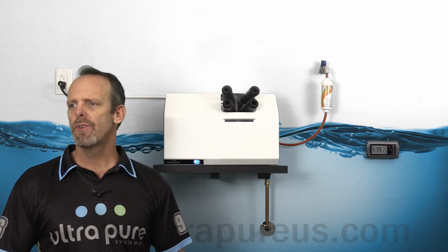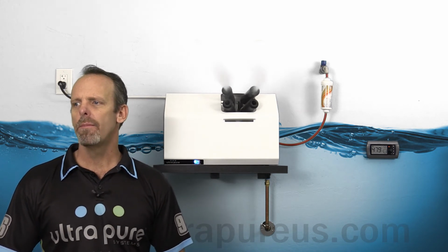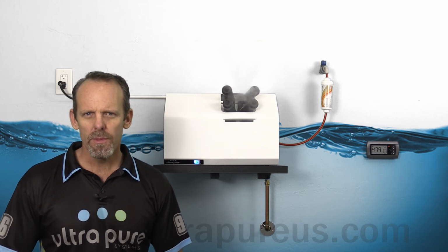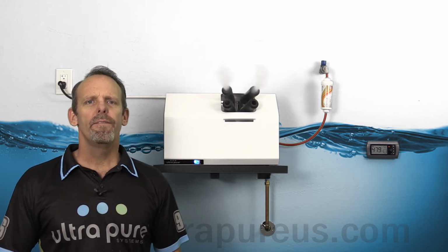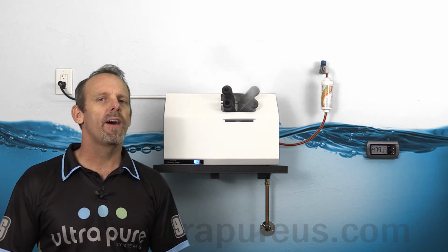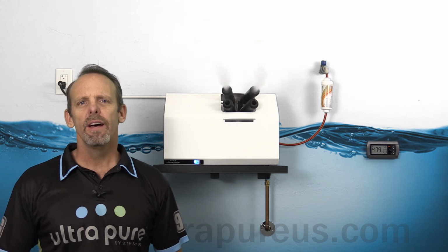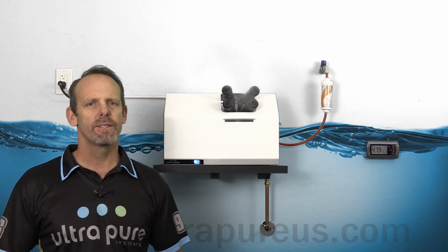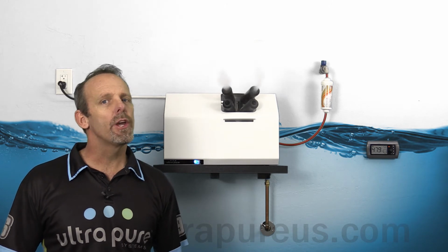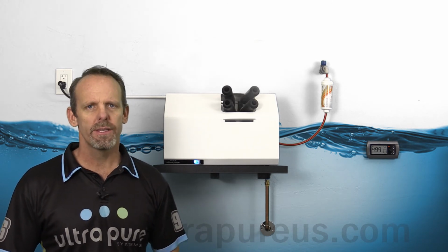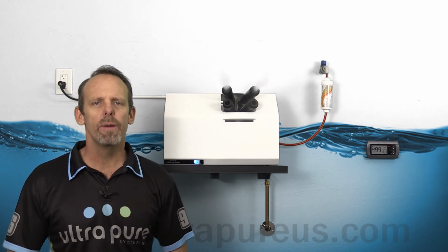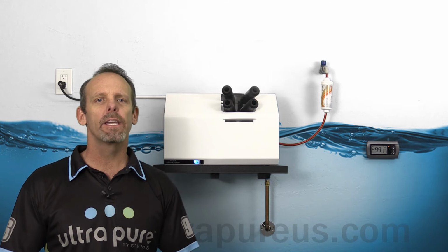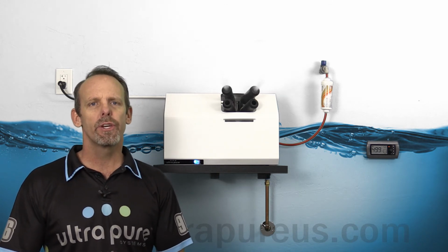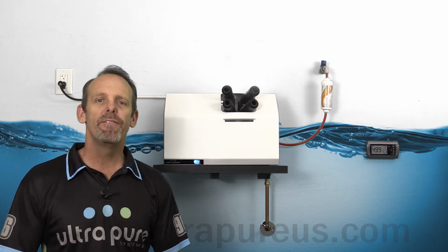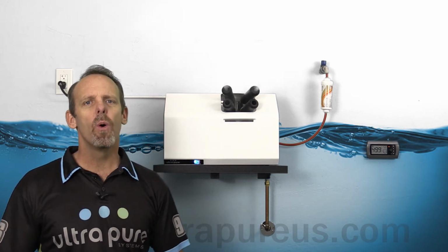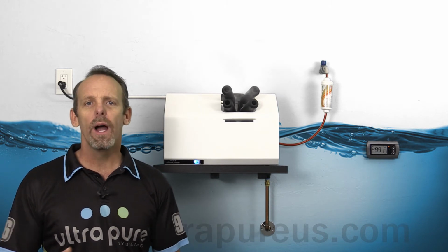What are the steps and procedures for level 3 and 5 commissioning of the direct wall-mounted humidifiers? That came from Dan in Arizona. Great question — we've had the opportunity to do level 3, 4, and 5 commissioning on these actual humidifiers. Level 3 and 4 is a great practice for end users, specifically owners who hire commissioning companies to come in, test equipment, and validate that if something can go wrong, it's captured, documented, and fixed before the space goes live — because the last thing we want is something going wrong with our humidifier in a live environment.